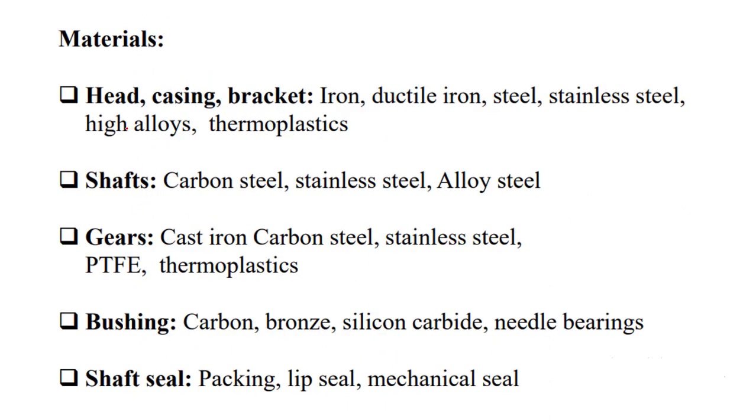Materials used for gear pump components: the head, casing, and bracket are made of ductile iron, steel, stainless steel, or various alloys. Shafts use carbon steel, stainless steel, or alloy steel — the choice depends on the fluid being handled; corrosive materials require stainless steel. Gears are made of cast iron, carbon steel, stainless steel, or plastics. Bushings use carbon, bronze, silicon carbide, or needle bearings — silicon carbide suits corrosive environments due to its resistance to corrosion. Shaft seals include packing materials, lip seals, and mechanical seals, generally made of rubber.